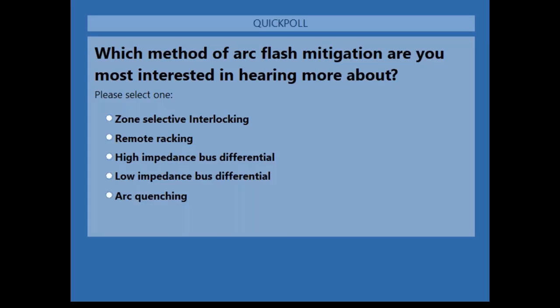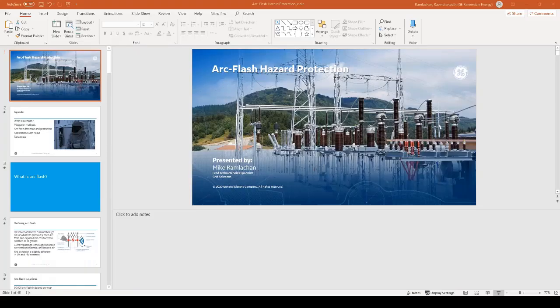So the low impedance percent differential: for most applications today, if you're building a greenfield project, the type of protection you'd probably select is the low impedance bus differential. But before we get into how we do low impedance bus differential, I just want to mention the challenges of protecting a bus zone. Obviously, we have high fault current levels, which, as we talked about, cause high incident energy, high arc flash energy, which can cause all of the mechanical issues and personnel safety issues. But there are also CT saturation issues that we have to deal with when we're talking about differential protection.